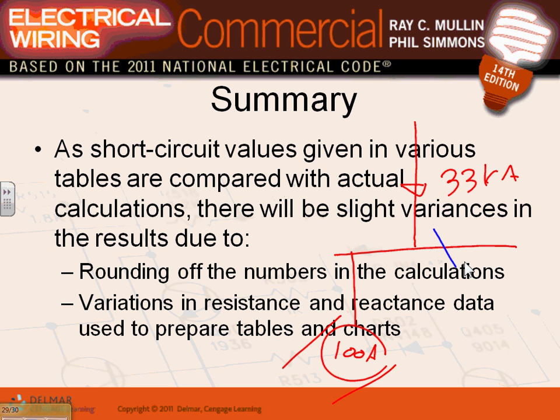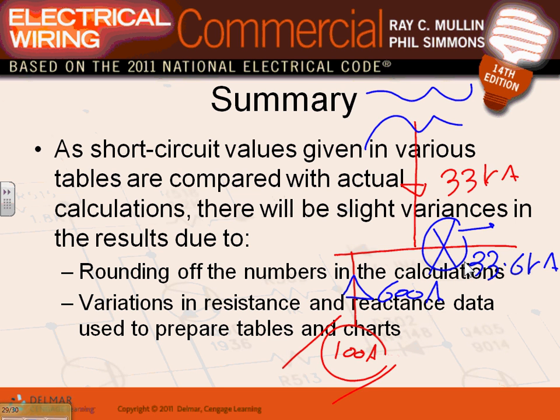If you have a short circuit right in here, guys, you know what happens? If I have a short circuit right in the panel, that air handling unit starts pumping current into the circuit. So it will contribute equivalent to its start current. The start current is usually 5 to 6, let's just say 6. So that will be 600 amp. So the total short circuit right here becomes 33.6 kiloamp. Can you guys see it? This is coming from the transformer, and this is coming back from the motors. So long story short, if you have motors, air handling units, chillers, rooftop units, all these pumps, when you have a short circuit, momentarily they change into a generator and they start pumping more current into the short circuit.